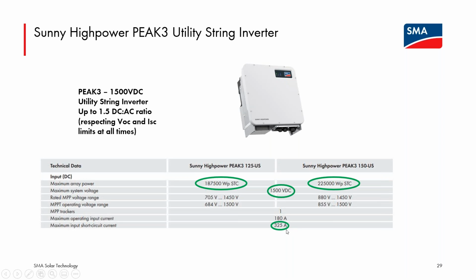Very similar to the CORE1, on the data sheet you see a maximum array power for each unit that you can go up to, as long as the open circuit voltage and short circuit current limits are not exceeded. And the math is the same, 1.5 ratio for the PEAK3 like the CORE1. And the process is similar if you wish to exceed that.